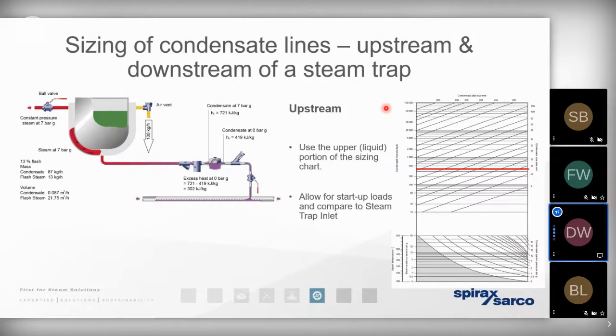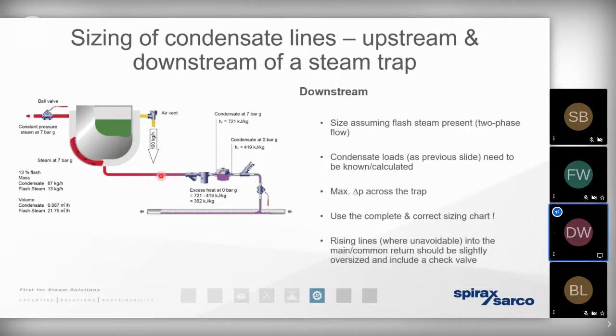The thing to bear in mind is what actually happens once the steam has pressurized the condensate and moved it downstream of the trap. It's at this point here that we're going to see a fall in pressure. So going back to those steam tables, using the example of 7-bar gauge, the sensible heat present in the condensate at 7-bar is 721 kilojoules. With a fall in pressure downstream of the trap to 0-bar gauge, the sensible heat of the condensate is 419. So that means there needs to be a significant fall in energy at the same time as there's a fall in pressure of the condensate moving across the trap.